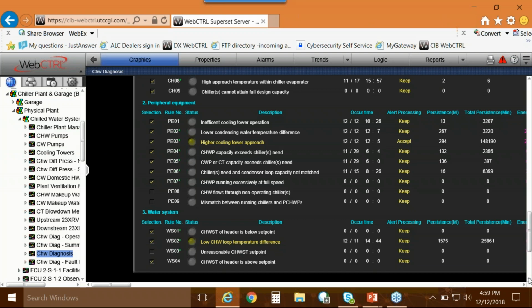What we want to do is say, you bought our chillers, you bought our service contract, we can sell you smart operation of the chillers, we can sell you fault detection and diagnostics for the chillers. We can even sell you a program that watches how much energy you're spending to make the chilled water, then look at the building's fans and pumps and find out how much energy you're using to utilize that energy, and we will play with set points so that the sum of the two is the lowest number, actively and dynamically throughout the day. There are guardrails on it so we don't ruin relative humidity control in the space and things of that nature. But the effort is saying, I've got data, what am I going to do with it?